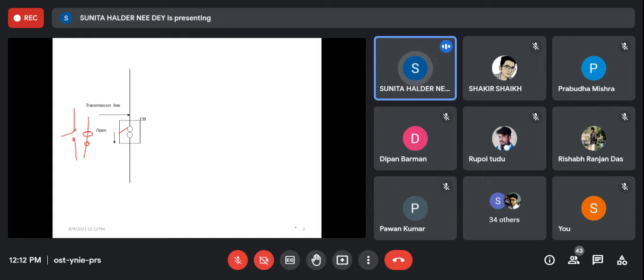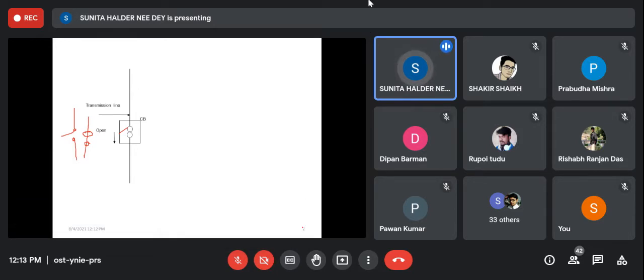But here we have to keep in mind that this is not as easy as an electric circuit in our lab, because here current is huge, in terms of hundreds of amperes. For a long line, the current is 300 ampere, 400 ampere like that. And when there is a short circuit, the current is far higher than that. If the normal current is 1 per unit, then the fault current is 5 per unit, 6 per unit like that. So if the normal current is 500 ampere, then the fault current will be 2500 ampere. That means 2.5 kilo ampere.